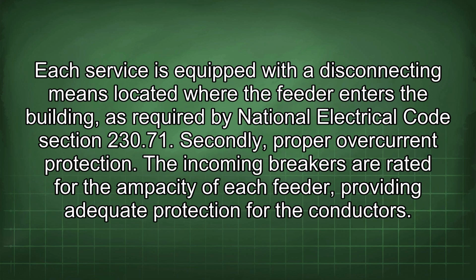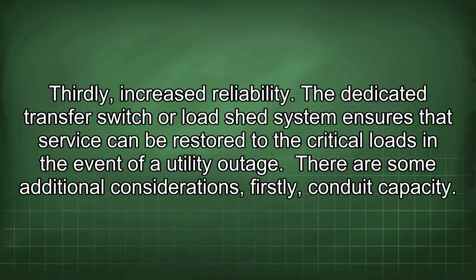Each service is equipped with a disconnecting means located where the feeder enters the building, as required by National Electrical Code Section 230.71. Secondly, proper overcurrent protection. The incoming breakers are rated for the ampacity of each feeder, providing adequate protection for the conductors. Thirdly, increased reliability. The dedicated transfer switch or load shed system ensures that service can be restored to the critical loads in the event of a utility outage.